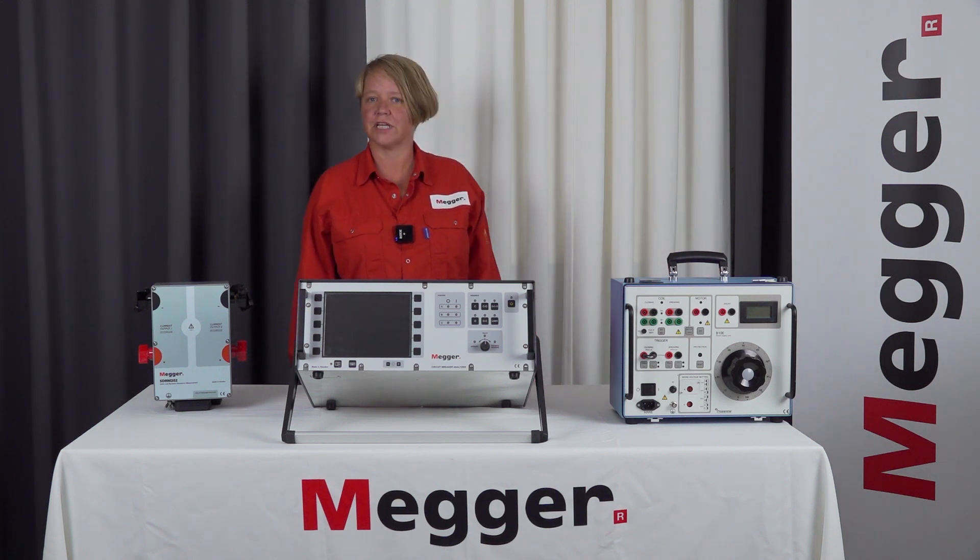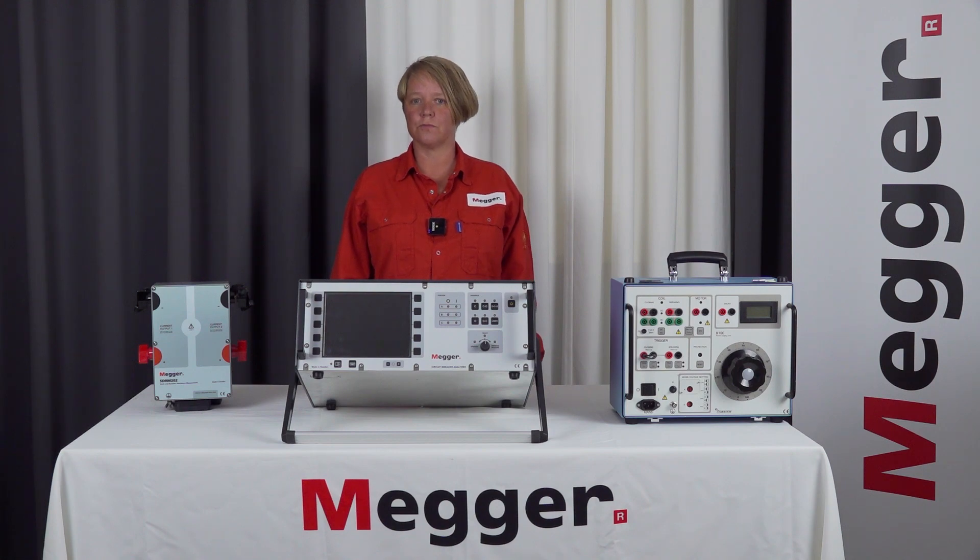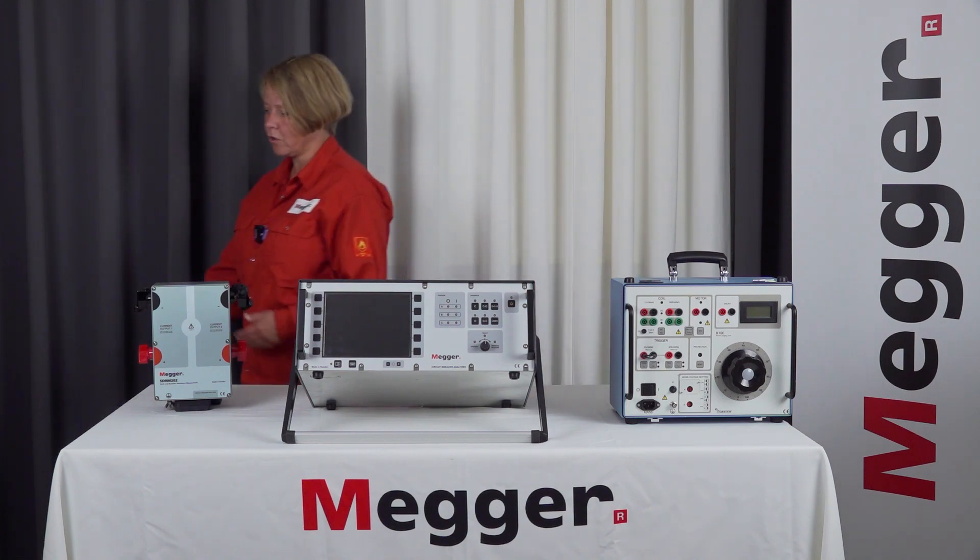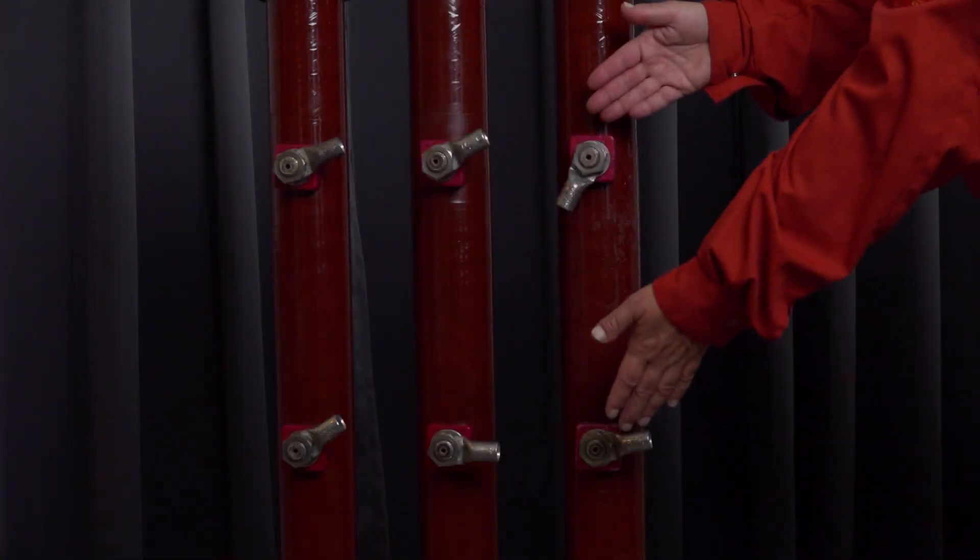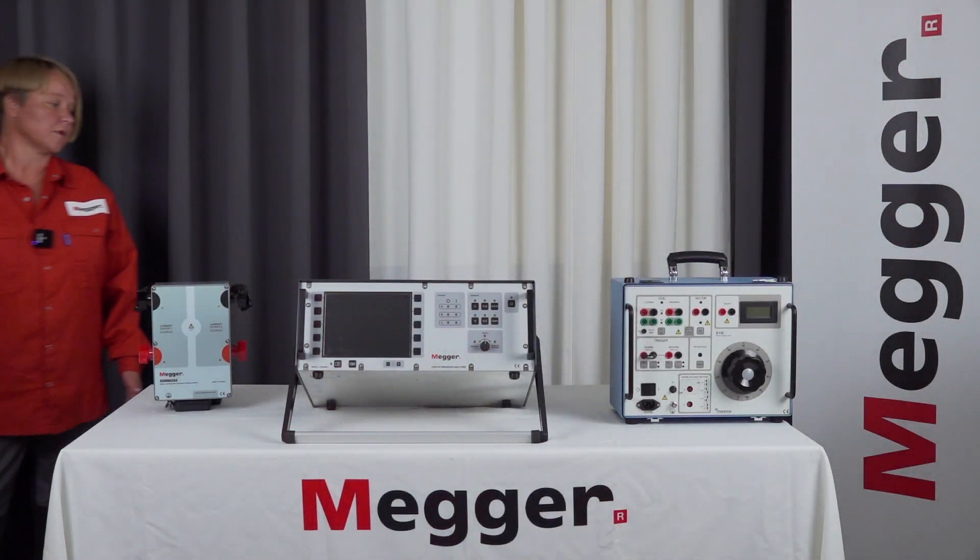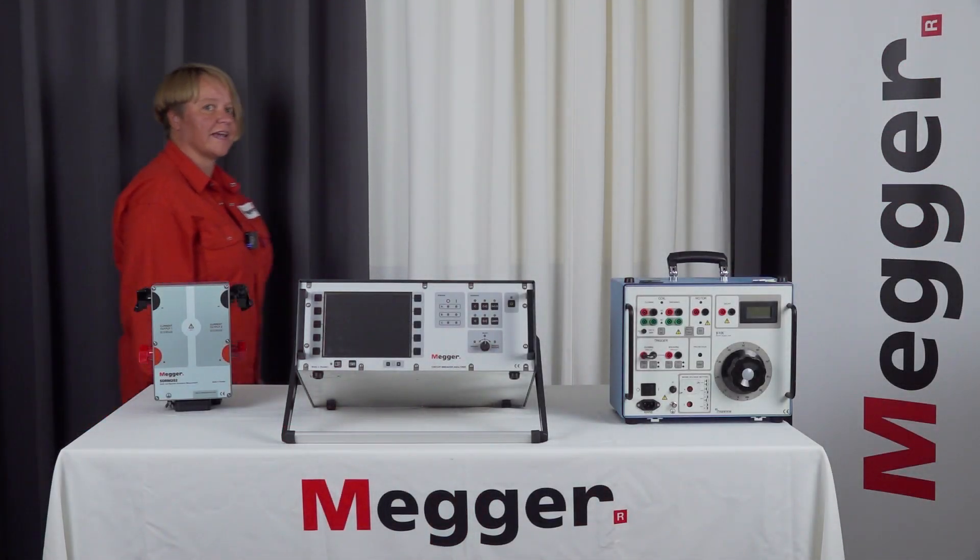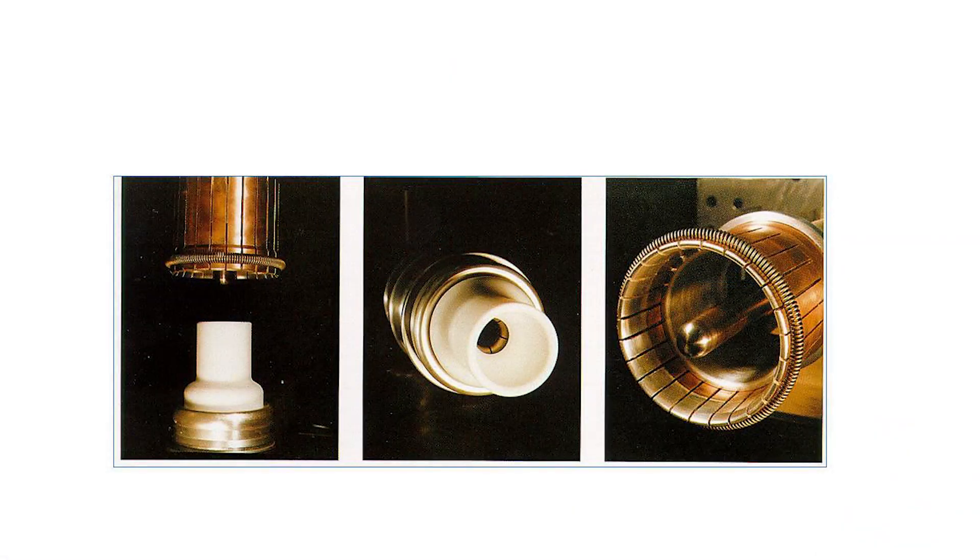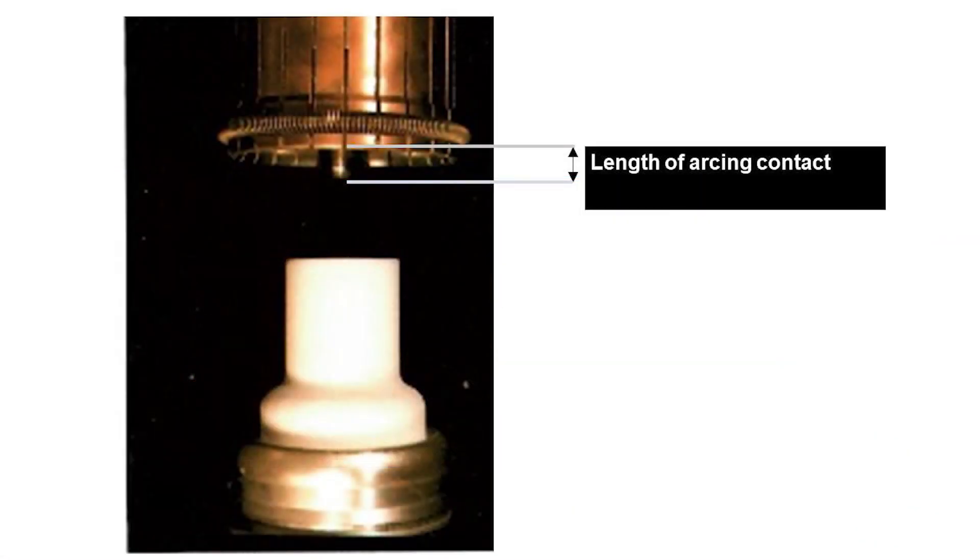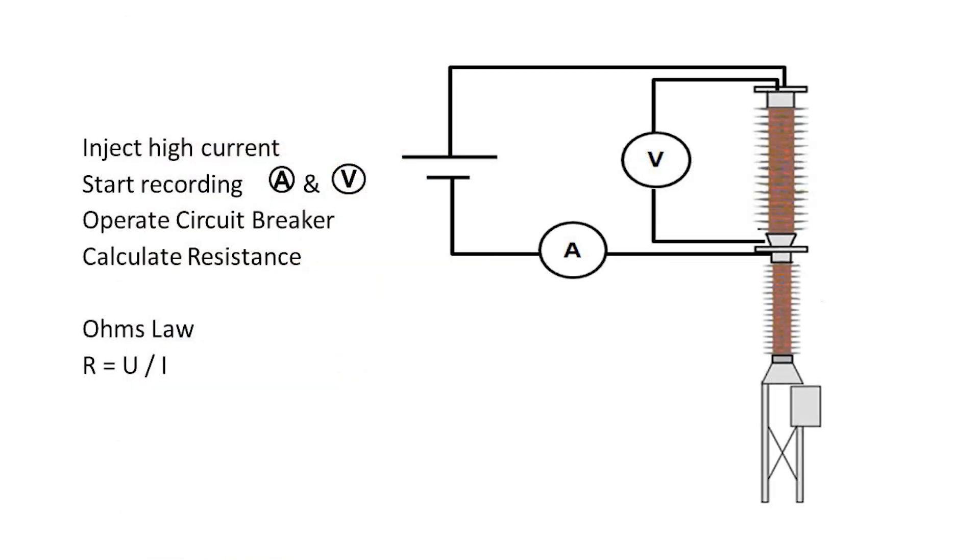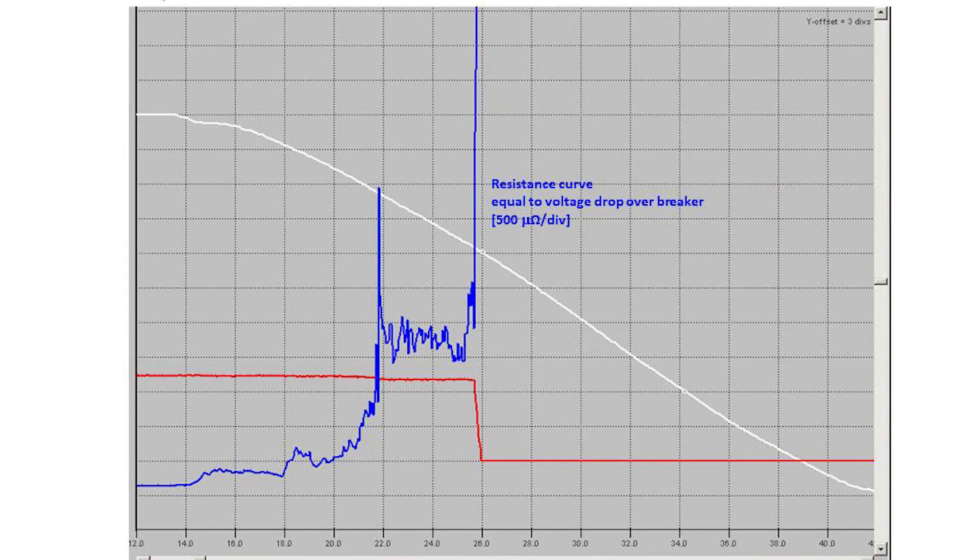The method DRM - you measure on the main contacts of a circuit breaker between the two contact points. You detect the inside of a breaker to analyze the details, mainly the arcing contact length. You measure voltage, current to calculate the resistance and you also measure the motion. By that you can see details of the arcing contact.